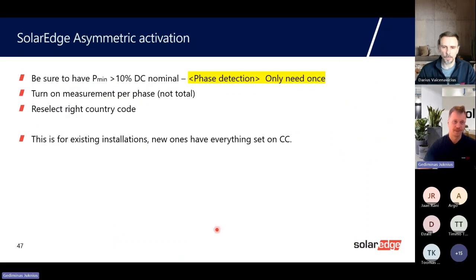And here I also want to mention a few things about asymmetry. For the sites which were installed last year, the only ones that support asymmetry are the hybrid Home Hub inverters. If you want to activate asymmetry, first of all, you need to be sure you have more than 10% of DC nominal. So basically, if you have a 10 kilowatt inverter, it should produce at least 1 kilowatt for phase detection. It is only needed once. Then you need to go to the energy management settings and set the measurement to per phase, not total. Then you need to reselect the country code, either Estonia, Latvia, Lithuania, or Finland. And that's it. For new installations, you don't need to do anything. You will set, for example, the country code Estonia, and asymmetry will be activated immediately. So that only applies to the old installations.